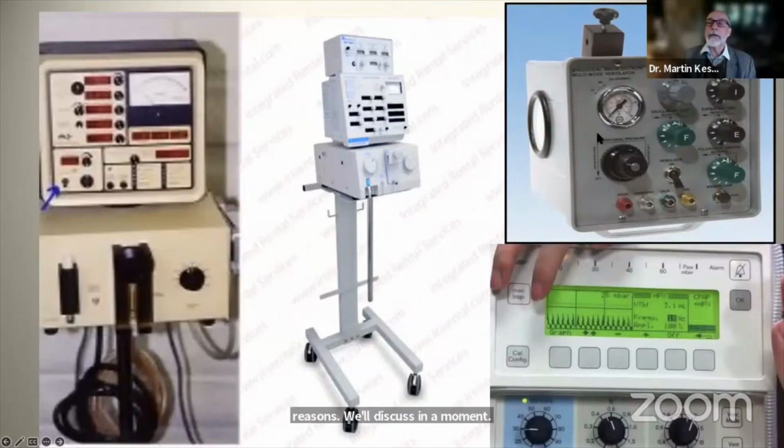The Bronchotron is a US device and is not available elsewhere. The old Babylog was somewhat of a hybrid between an interrupter and an oscillator. It did generate mostly adequate expiratory deflection, but it was not a powerful enough oscillator. In some circumstances, it had limitations.